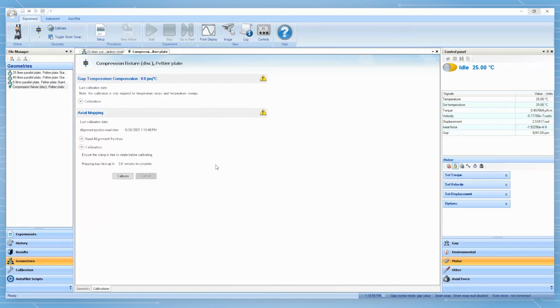After this is done, perform axial mapping calibration on the plate. This axial mapping calibration is important for all DMA mode testing. This calibration measures the mass of the upper fixture and also linearizes the displacement output of the instrument magnetic bearing. This axial mapping will take about 3 minutes to complete. After all the calibration is completed, close this page.